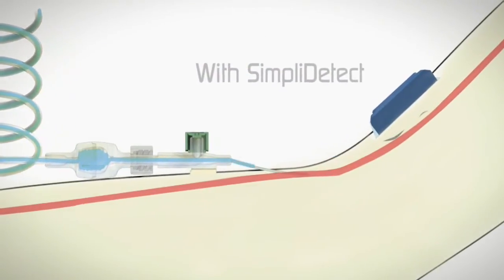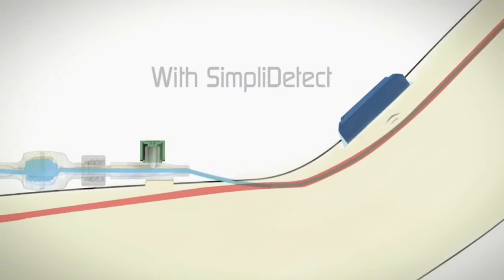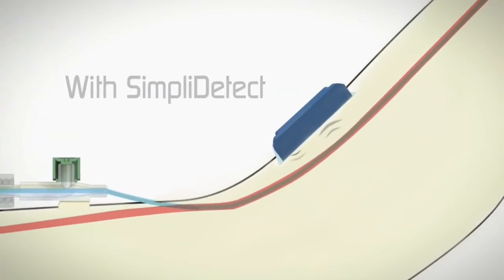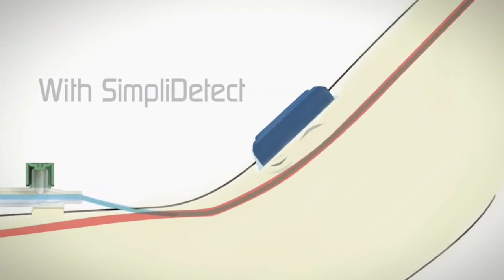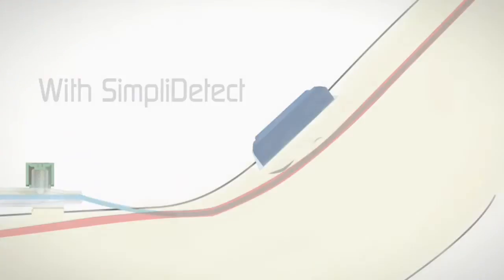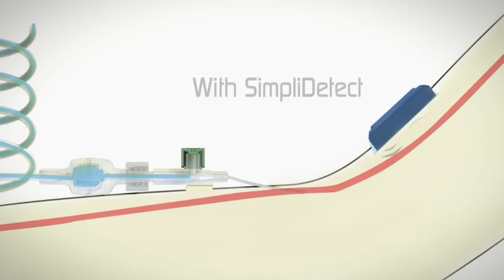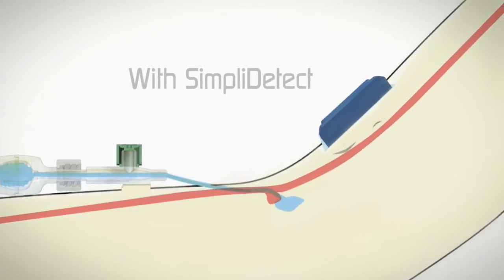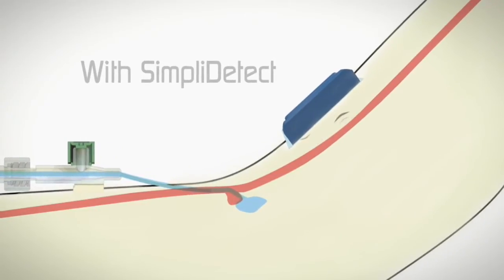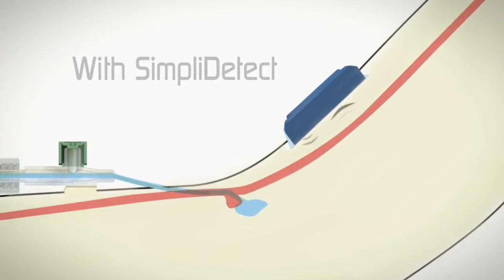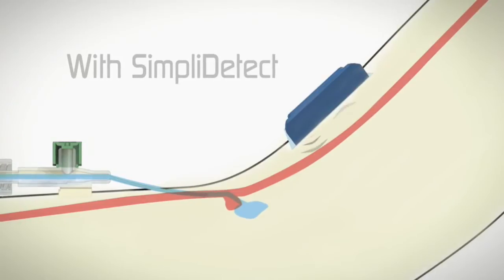Using Doppler ultrasound, SimpliDetect registers the increased flow attributed to the injection of the contrast media, or saline solution. If for some reason an increase is not seen, the injector will automatically be shut off and an alarm will sound, prompting the CT tech to take corrective actions.